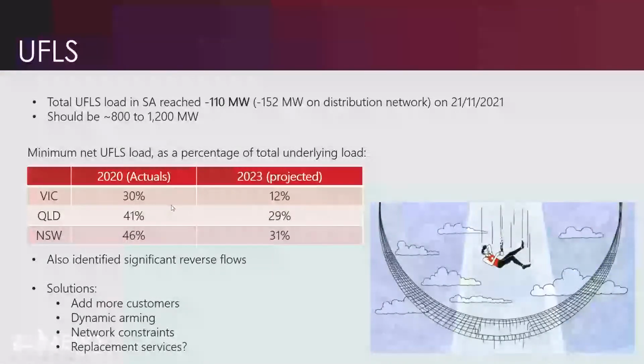So these are actual values measured in 2020. We saw Victoria get as low as 30% of underlying load, and it should be up around 60%. Queensland as low as 41%, and New South Wales as low as 46% of underlying load. So these are all in the middle of the day in very low demand periods. We're seeing UFLS load dropping considerably right across the NEM.